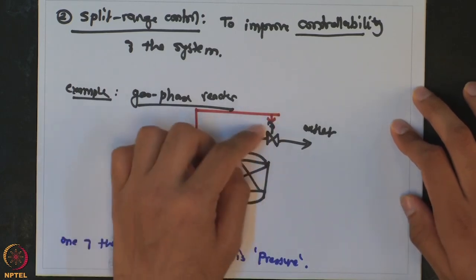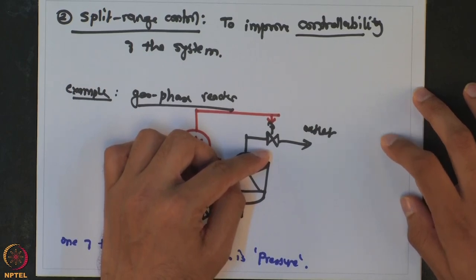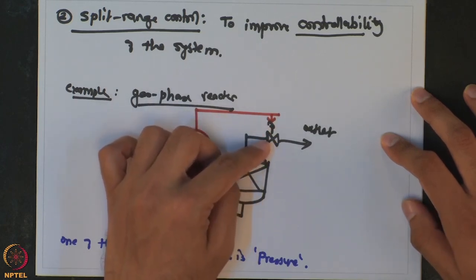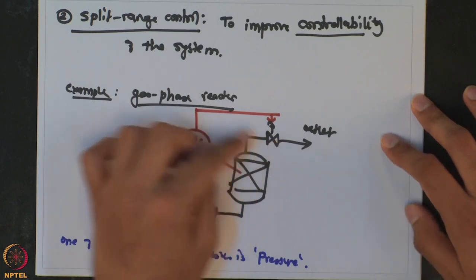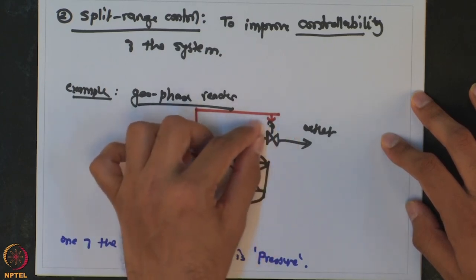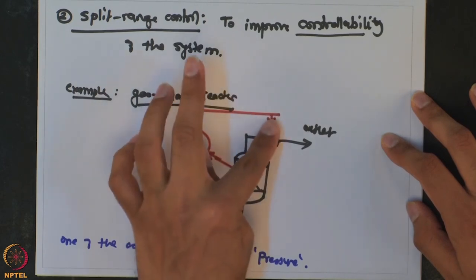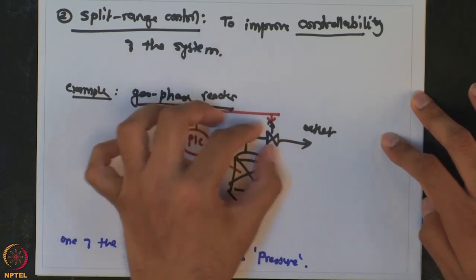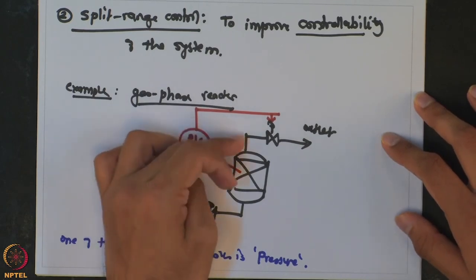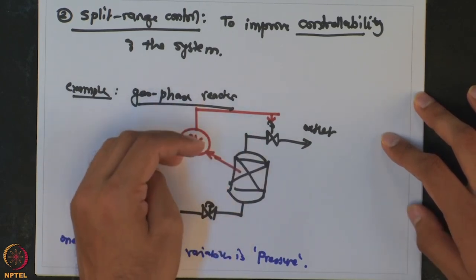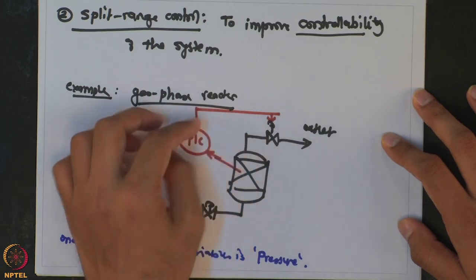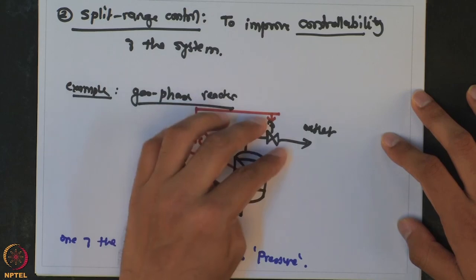As the pressure increases, you open the outlet valve, but there is a limit — the maximum is when the valve is completely open. At that point, the resistance is dictated by how much vapor the pipeline can carry. Even with the valve fully open, it is as if there is no valve and the entire pipeline carries vapor out. But in a runaway situation with a lot of vapor being generated, this may not be sufficient. The pressure keeps building because you can no longer manipulate it — the manipulated input is saturated and you have lost controllability.